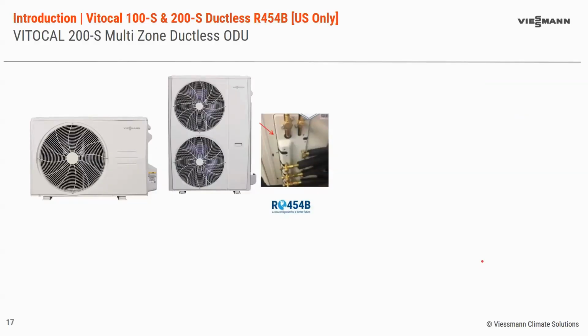So the multi-zone outdoor unit shown here visually, if you're standing far away from it, you're not going to see much difference than a single zone. But when you get closer, you'll notice there's multiple connection points as shown below. So there is not a branch box on our multi-zones. Everything lands back at the outdoor unit. So as mentioned before, 18 to 55,000 BTU range, up to 6 zones. We'll touch on the next slide how many zones for each capacity. And that's also listed in the product information, the installation manual, the product data, as far as compatibility and application options.